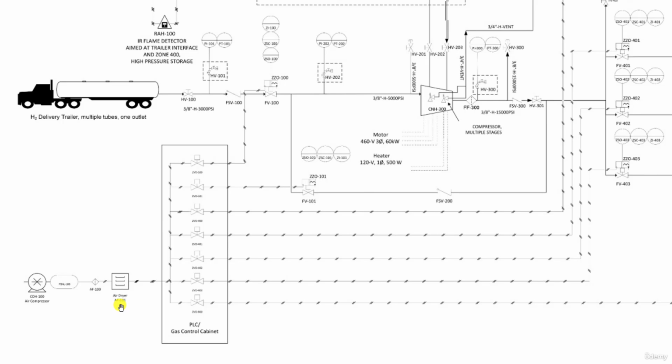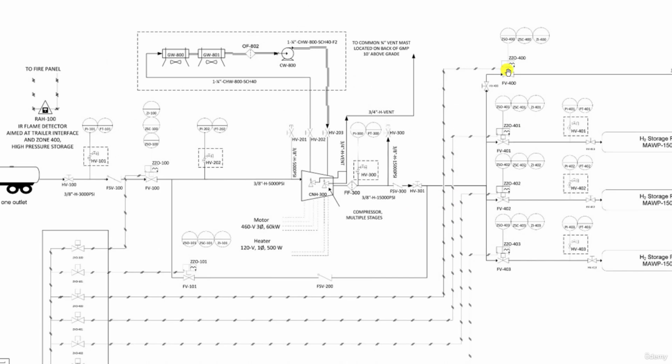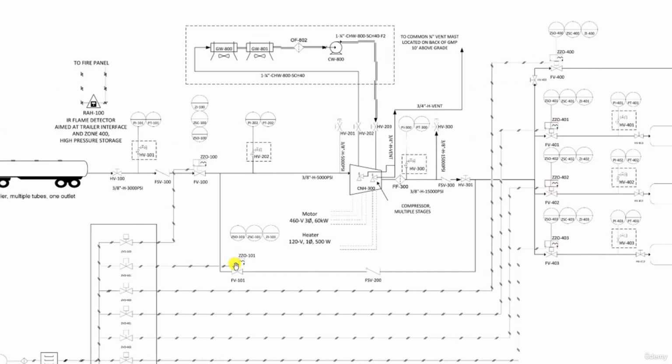Now, why is this system part of the safety system? How do we know that? The answer is quite obvious. The instrument air is supplied to single-acting spring-return close actuators on the process valves. This means that these valves remain in the open position as long as the actuators are supplied with instrument air.